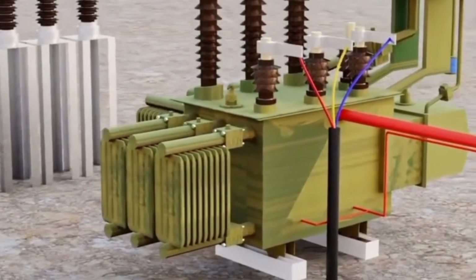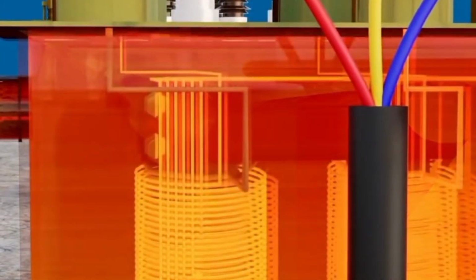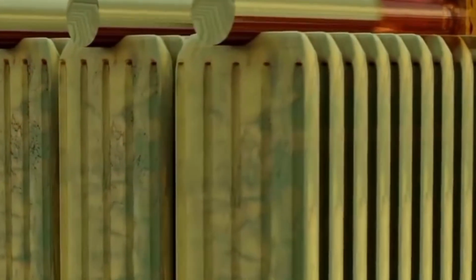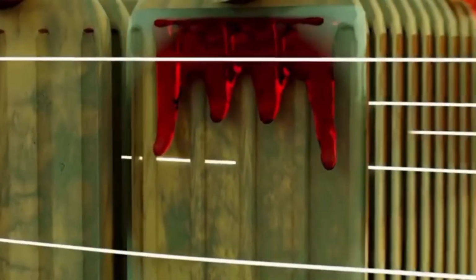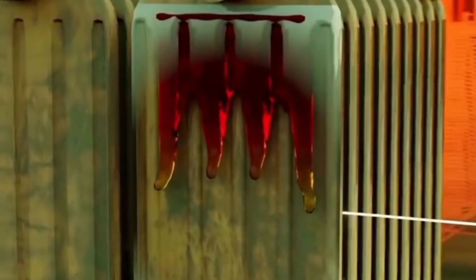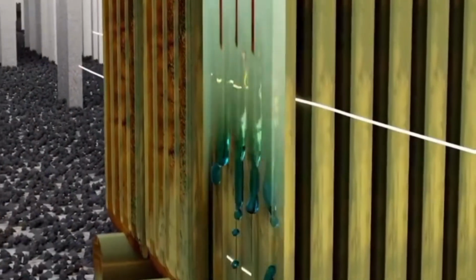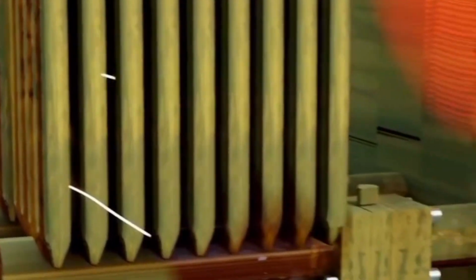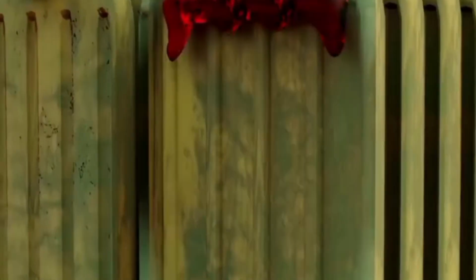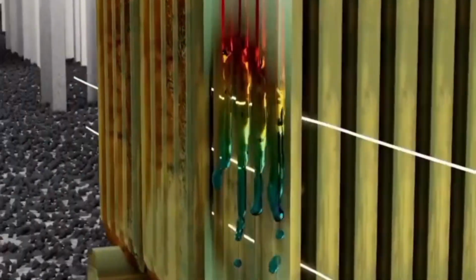In a real-world substation environment, these internal components are supported by heavy-duty external infrastructure designed to handle immense electrical stress and environmental elements. The massive bushings protruding from the top of the transformer act as insulated pathways that safely guide high-voltage overhead transmission lines into the sealed tank without grounding out against the metallic frame. Because the process of changing voltage still generates a considerable amount of heat despite the laminated core, the entire tank is filled with a specialized insulating oil. This oil serves a dual purpose.